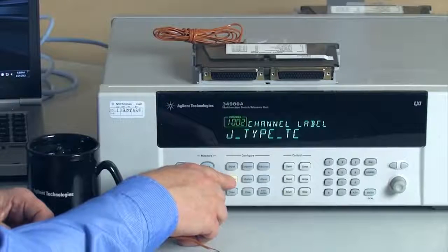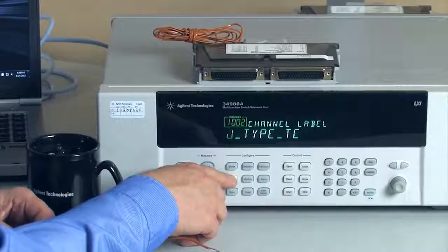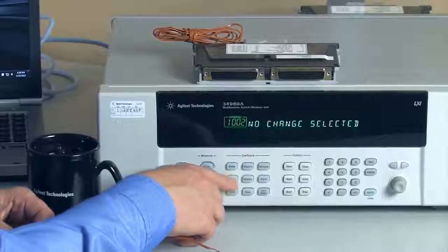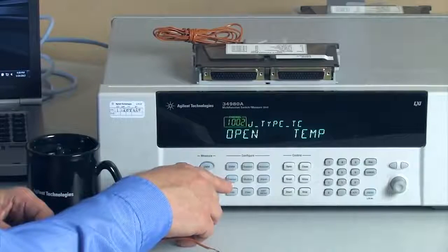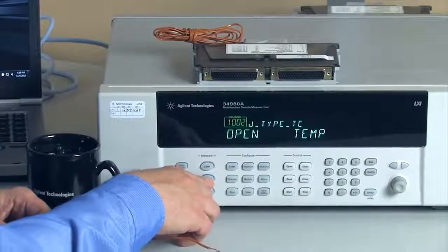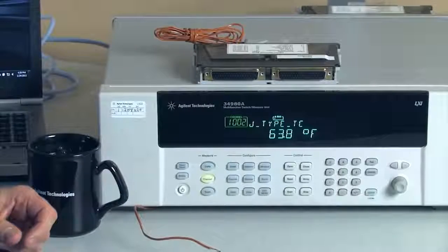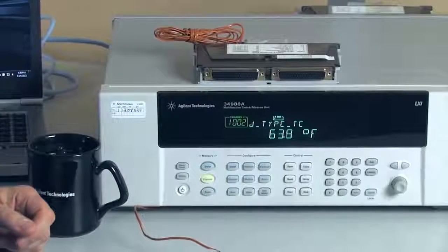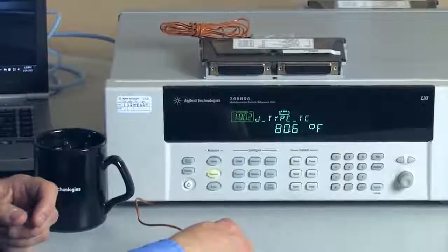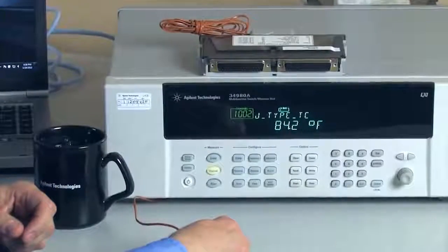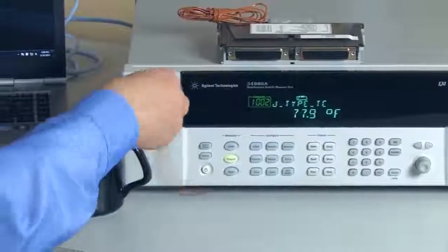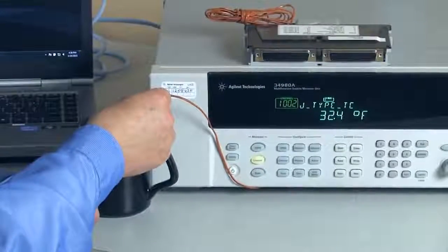At this point, we can name the channel, which I've already done as a J-type TC. Now the temperature channel is configured. To make a measurement, we simply hit the temperature channel key. It is now measuring the temperature. Notice when I grab hold of the thermocouple, it goes up. Or when I put it in an ice bath, it drops.